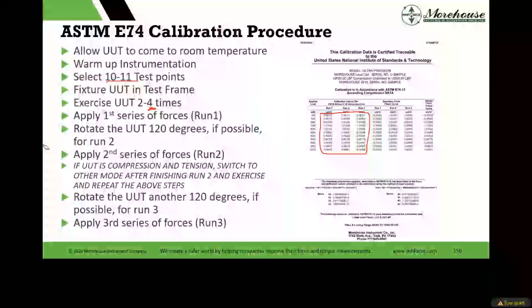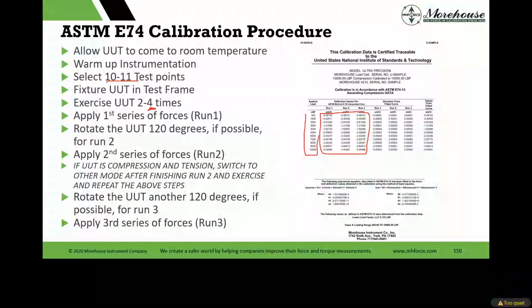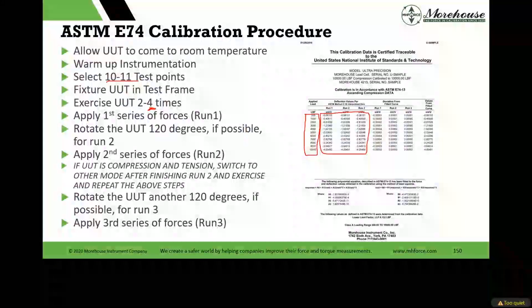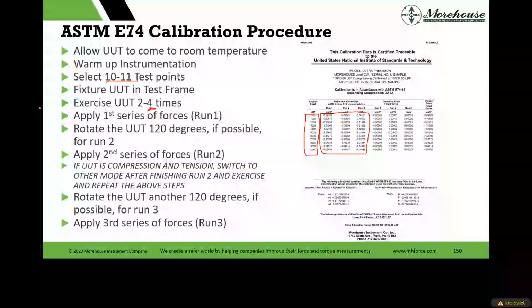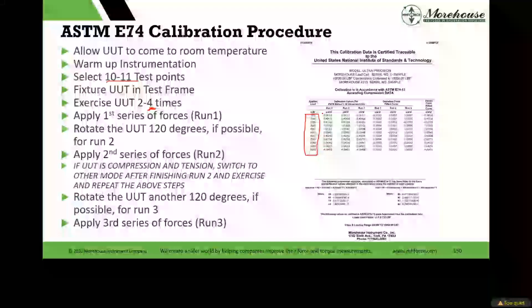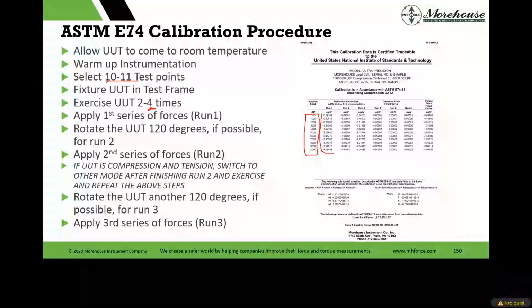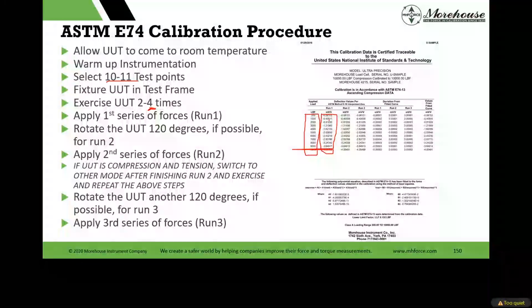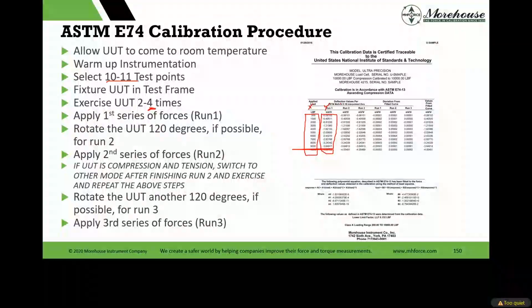They'll plot, and this is what you want to look at, because they'll want to plot these force applied values versus the average of these values. The way the standard is written is not that. The way the standard is written is very descriptive and clear. And I know I'm probably boring the other people, but the way the standard says is basically, the way I want to run my data, instead of averaging all this, I want to treat each set of data separately. So 200, 1000, this is my X and my Y, right? And then I want to redo this 200 to 1000, and this is going to be a Y, and this is going to be a Y.